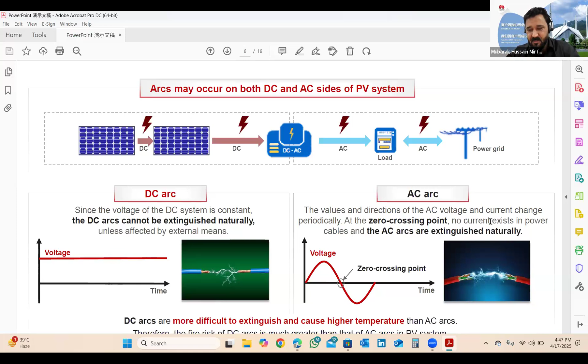Mostly where these issues or faults occur, these are the basic issues: mostly it's coming from the DC side, the arc faults are coming from the DC side. So it's always considered that any problem coming from the DC side is more hazardous than the AC side, as clearly mentioned in the slide, because AC current is a constant alternating current, which has some safety margin either for human lives or for properties, compared to DC. In the further slides, we'll be discussing these arc faults, fire incidents, and which kind of technologies have been integrated in the inverter to safeguard against these issues.